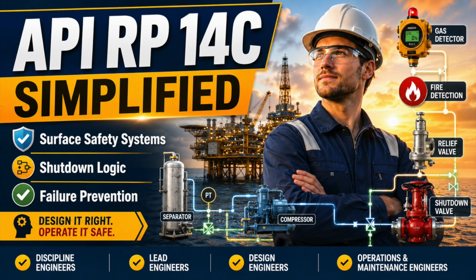A gas leak inside an enclosure may not create a meaningful process pressure change, but it can create a dangerous atmospheric concentration. The device must be derived from the physical failure, not copied from habit. High pressure requires detection and source isolation, plus independent pressure relief where required. High level requires enough remaining vessel volume for detection, logic processing, valve movement, and continuing inflow before overflow occurs. Low level requires enough retained liquid between the trip point and outlet to prevent gas blow-by before shutdown is completed.